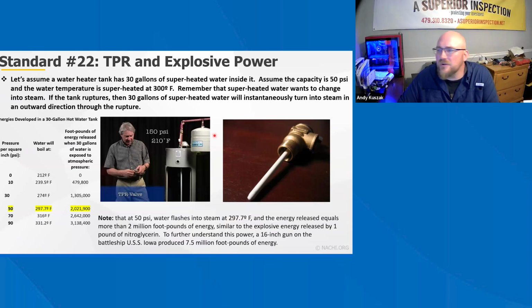We have another TPR, so we're going to go over this kind of quick because I think we're almost done here. To prevent heating the water above 210 degrees, the temperature pressure relief valve must be installed in the hot water within the top 6 inches of the tank. Water heater tanks usually have an opening in the tank shell installed by the manufacturer. In order to properly sense the tank's water temperature, the temperature pressure relief valve must be located in the tank within the upper 6 inches of the hot water, where all the hottest water is located. The location is more important for temperature than for pressure, since the pressure is uniform through the tank.